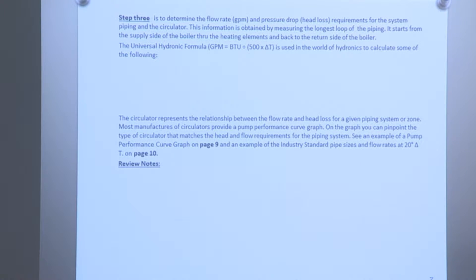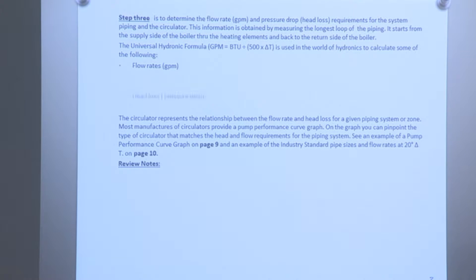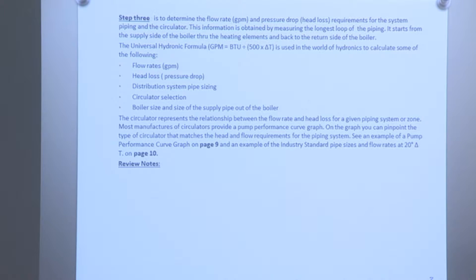Step 3 is to determine the flow rate in GPMs and pressure drop — head loss requirements — for the system piping and the circulator. This information is obtained by measuring the longest loop of the piping, starting from the supply side of the boiler through the heating elements and back to the return side. The universal hydraulic formula — GPM equals BTUs divided by 500 times delta T — is used to calculate flow rates in GPMs, head loss, pressure drop, distribution system piping sizing, circulator selection, boiler size, and size of the supply pipe out of the boiler.